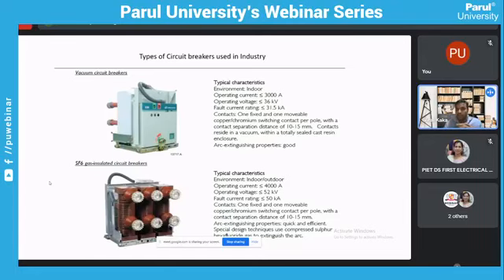The operating currents for medium voltage vacuum circuit breakers in a medium voltage switchgear can be 1600 ampere, 2000 ampere, 2500 ampere. It can go even to 3150 ampere with forced cooling. It can even go to 4000 ampere for a switchgear along with forced cooling. The switchgear also has the capability to interrupt faults up to 40 kA. It starts from 25 kA and then rises upwards from 25 to 31.5 and then 40 kA in terms of its fault clearing capability in switchgears.